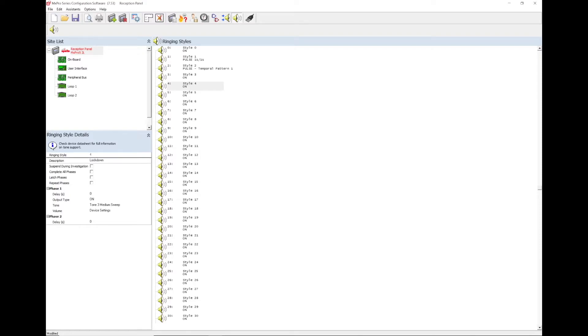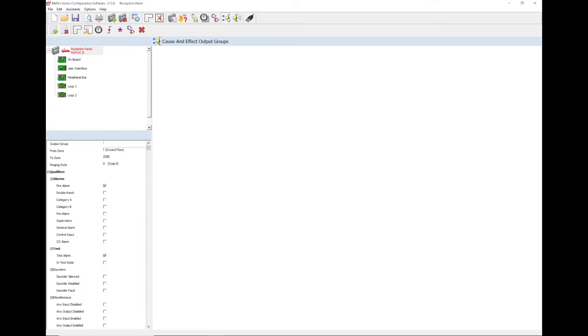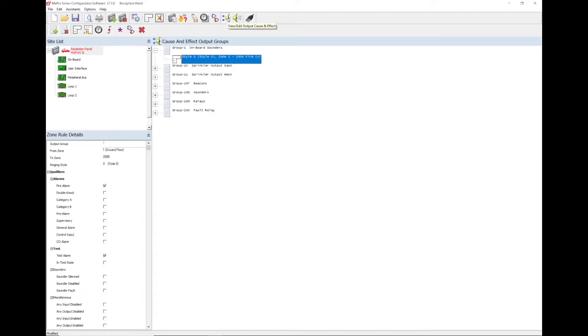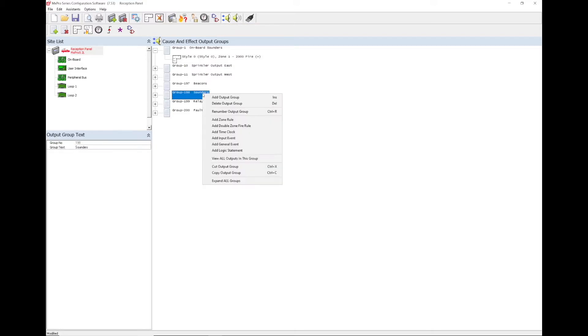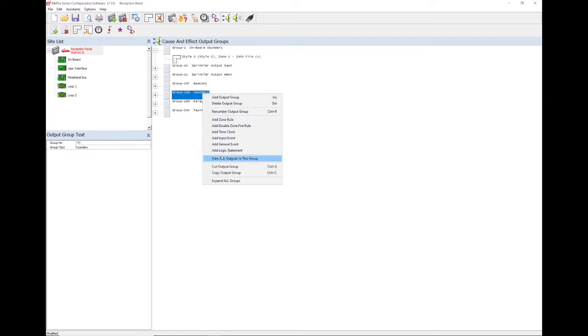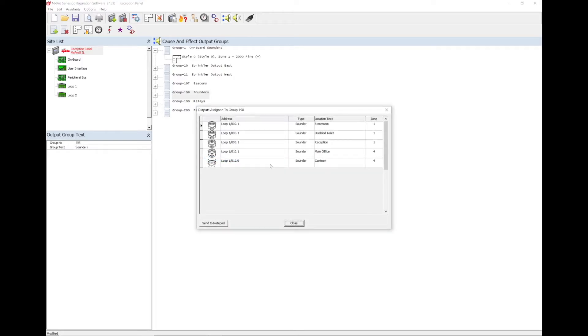Once this has been set up, go to view edit output cause and effect and right click on the output group for the sounders to add an input event. If unsure which output group the sounders have been assigned to, right click on an output group and select view all outputs in this group. The type of devices in that specific group will then be displayed.